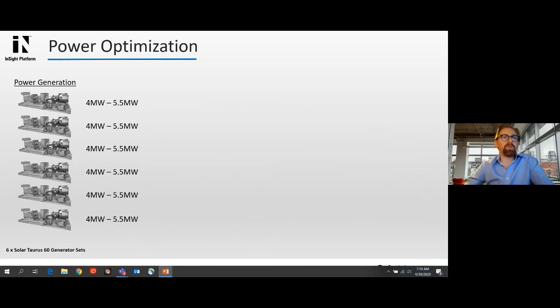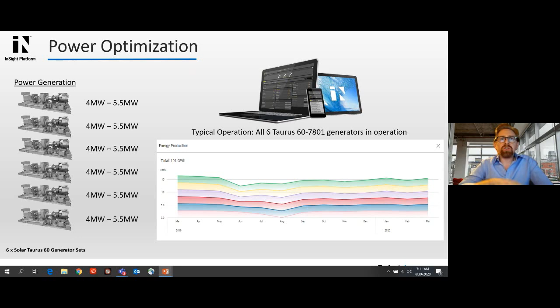In offshore installations, customers typically load up and run each power generation unit, equally distributing the load. Here I have a year's worth of data looking at the load profile. This customer's application is similar to those we see worldwide, with 6 engines all lightly loaded and sharing the electrical power needs for the entire installation.